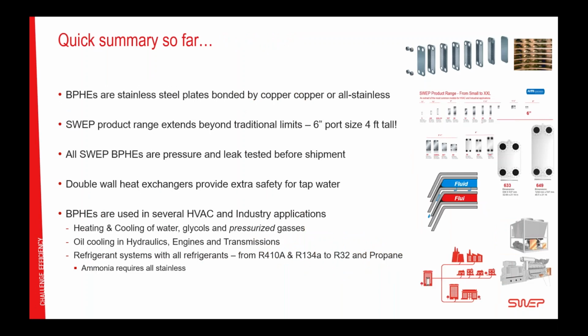I'll move on. Since this has gone pretty fast, I'll take a short summary. So brazed plates are stainless steel plates bonded by a filler material that is typically copper, or all stainless. The SWEP product range is pretty big, and it extends beyond what traditional limits say. When I speak with engineers, they say, well, a brazed plate is up to 1, maximum 2 inches of port. We have 6-inch port. So the capacity that SWEP can solve is well beyond what is commonly known on the market. All our heat exchangers are pressure and leak tested before shipment. Double walls provide extra safety for tap water.